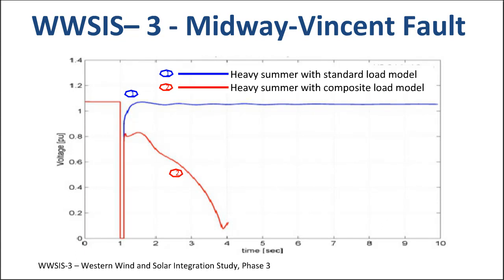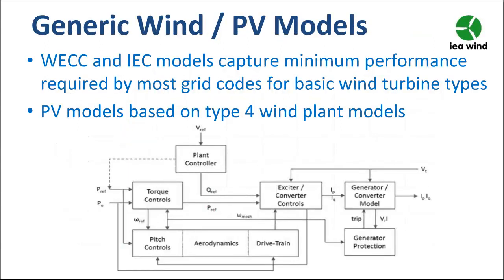This might seem quite complicated, but let me give a quick illustration of why you might want to look at your load models. This is an illustration from the Western Wind and Solar Integration Study. They applied a three-phase fault at a particular bus, and the blue trace shows the response revealed by simulation when using standard models. You can see there's a voltage dip and then the voltage quickly restores and everything looks fine. But whenever you use a more sophisticated load model, you get the red line, and there's a very large difference between the red line and the blue. So the blue line is giving you false confidence about what actually might happen.